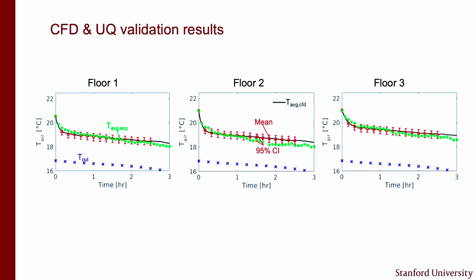This is what we get on floor one, floor two, and floor three. The green is the average temperature in the experiment, the black line is the CFD, and the red with confidence intervals is just the CFD showing the confidence intervals. This is the outdoor temperature decrease. You clearly see that these models can do a very good job at predicting that average indoor temperature, but only if you have really representative measurements.